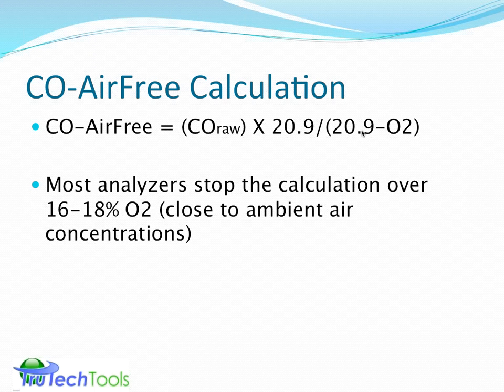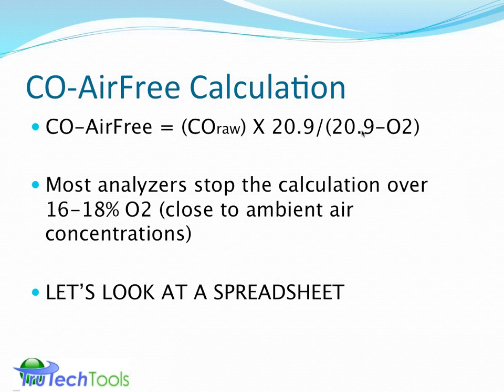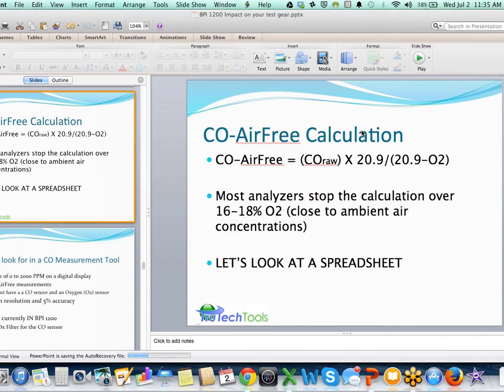This calculation here, we'll take a look at a little calculating spreadsheet, which I'm still in the refinement stages of, but plan to circulate it to people once I can get through my quality control checks on the spreadsheet and make sure it's pretty bulletproof for everybody to use. But I'll show you a working prototype of that spreadsheet. I know a couple people out there are hankering to get their hands on it. Most analyzers do stop the calculation over 16 to 18% oxygen because it gets so close to ambient air conditions, it's really not a flue gas type measurement, and pretty high numbers are involved. So let's take a second here and we'll jump out and take a look at Bill's spreadsheet.